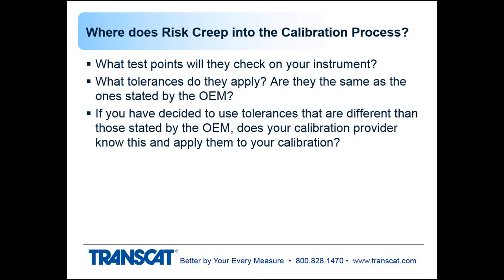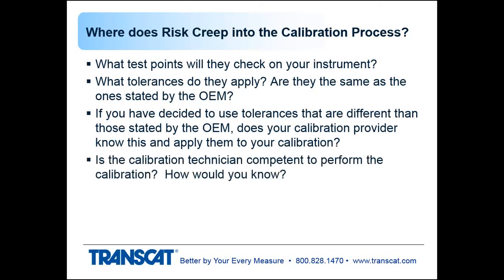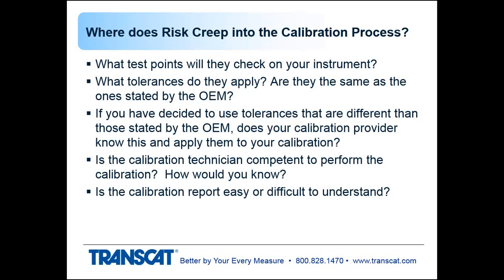This all ties together to suitability of the instrument and understanding how that is acceptable for the application where the instrument will be used in your process, and making sure the cal lab is supporting the test points and tolerances that are needed to keep that suitability decision intact and not affect your product decisions. Technician competency for the person that does the calibration. How would you know if they're competent? It's really your suppliers' or your internal lab's job to make sure the technician is competent. But ISO 17025 is one process where competency is assessed independently. What about the cal report that you receive? Is that easy or difficult to understand? Is it laid out well and easy to apply?